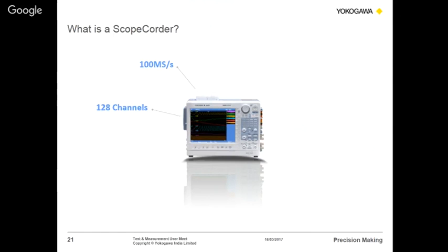High speed glitches can be captured. Many different types of triggers are available. AC voltage and current can be measured, from millivolt to kilovolt. Directly you can feed the signal, no need of any probes - directly up to 1000 volts, 1 kilovolt, you can feed to the equipment.